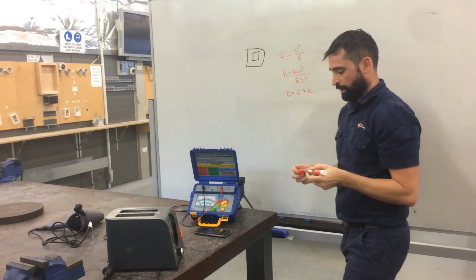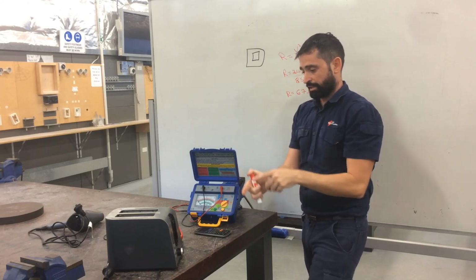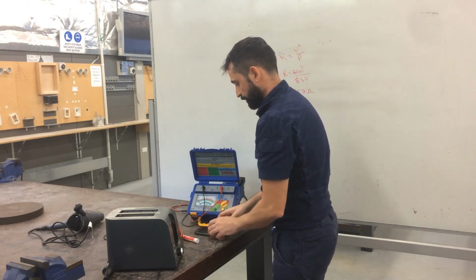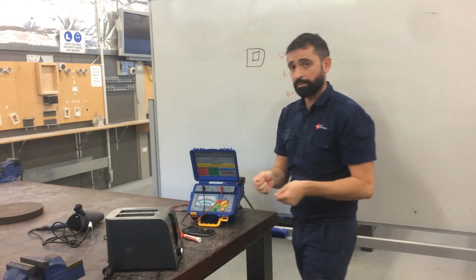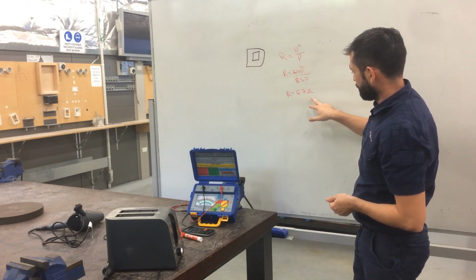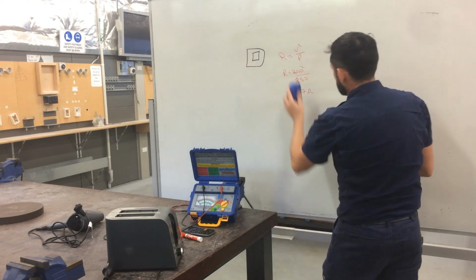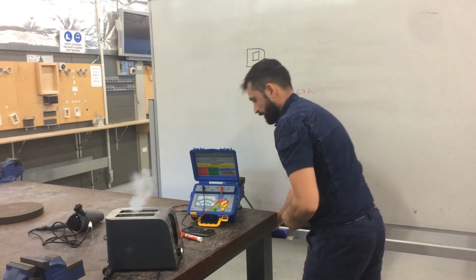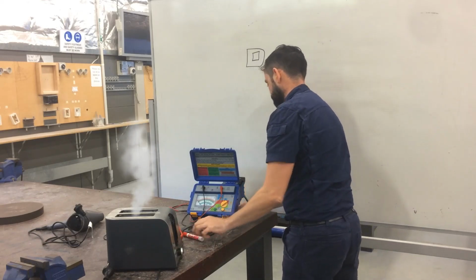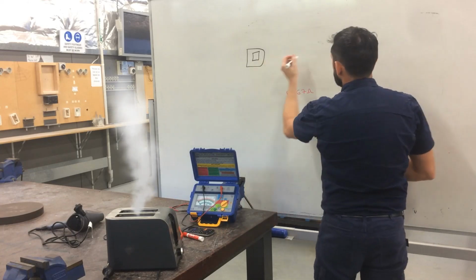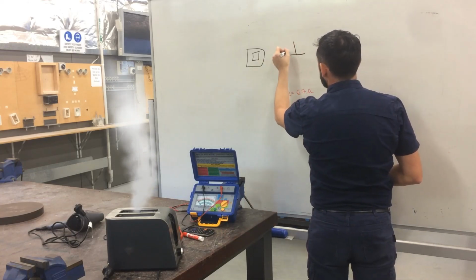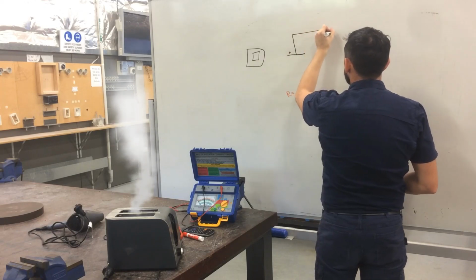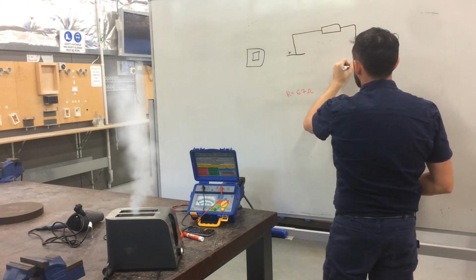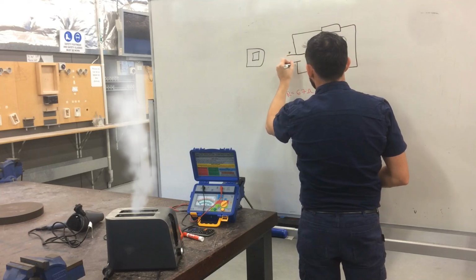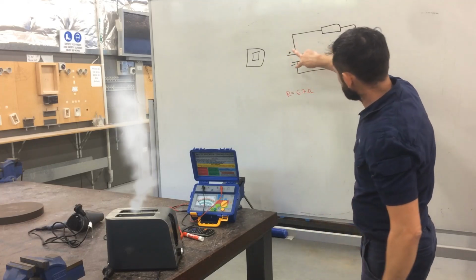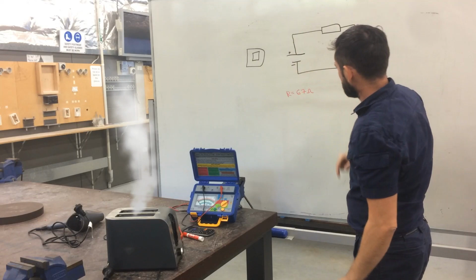Now we know what we're looking for. We can go and check the active and neutral terminals on the plug top, and we measure between them, and we should get about 67 ohms. But something we have to pay particular attention to is, let's put this toaster in as a circuit. So what we have here is a plug top, there's the positive side. Let's say that's our toaster, and we're coming out, and there's a negative. Okay? So we're saying that the total resistance of this, by calculating it, is going to be 67 ohms.